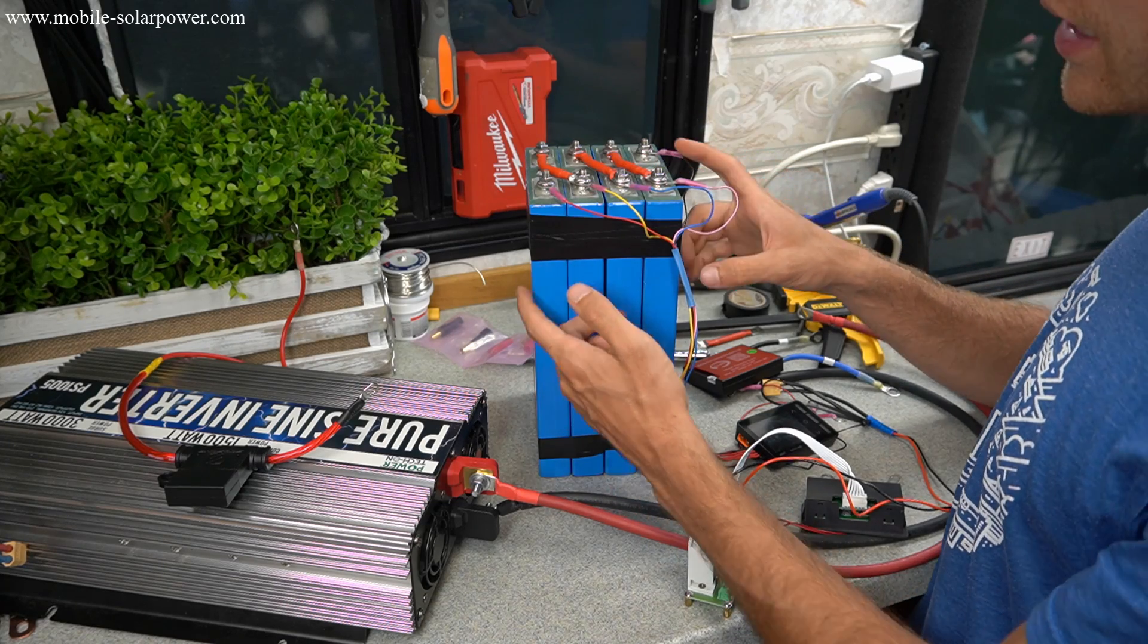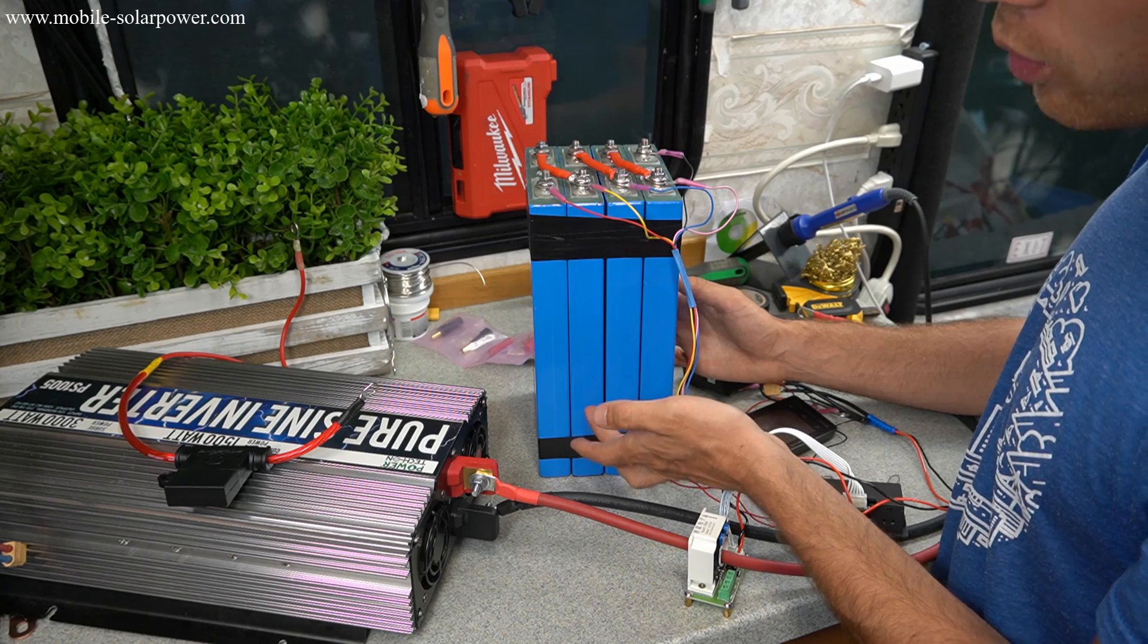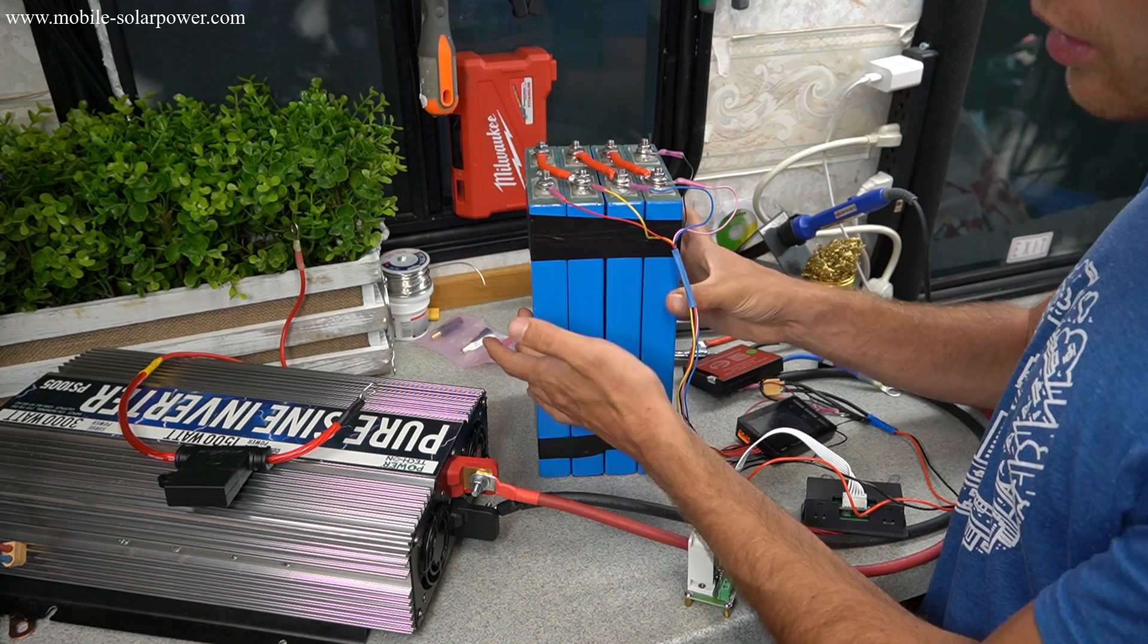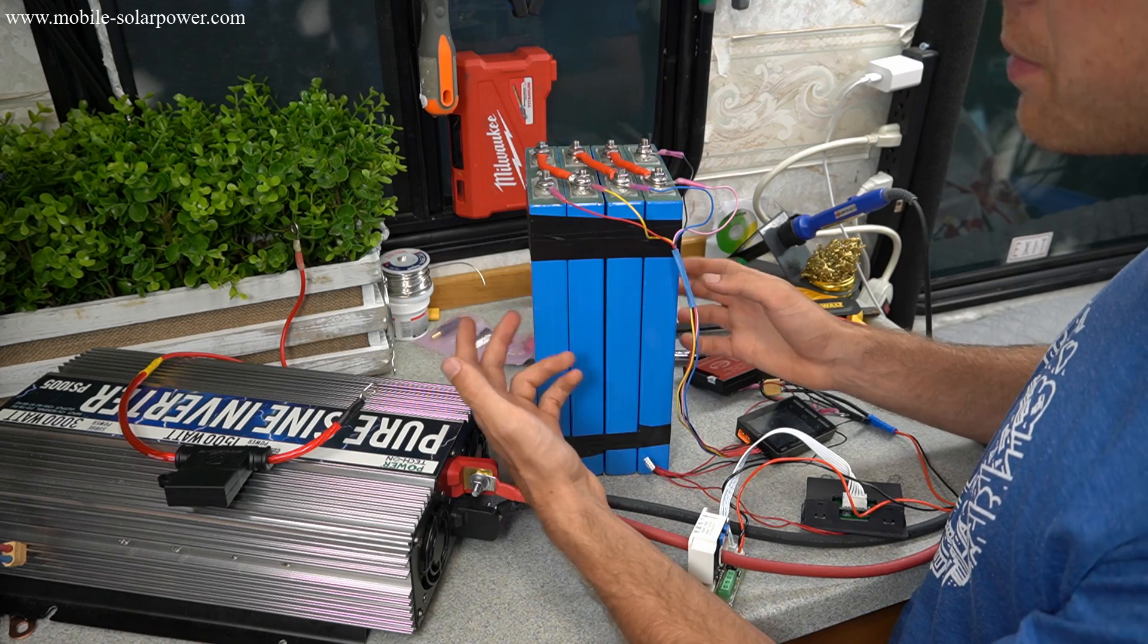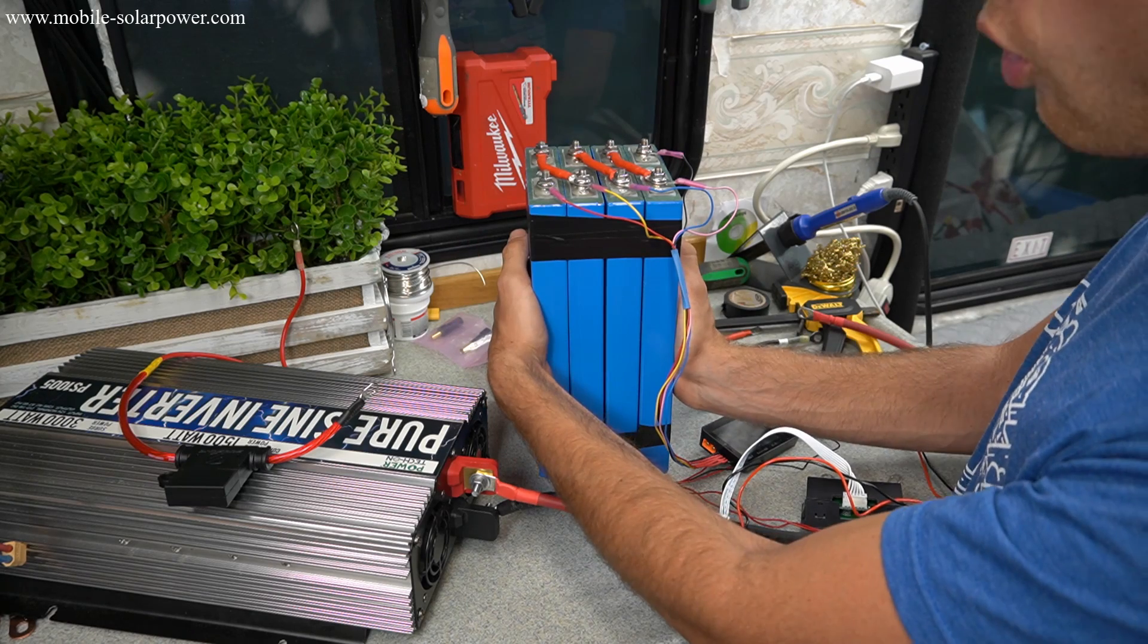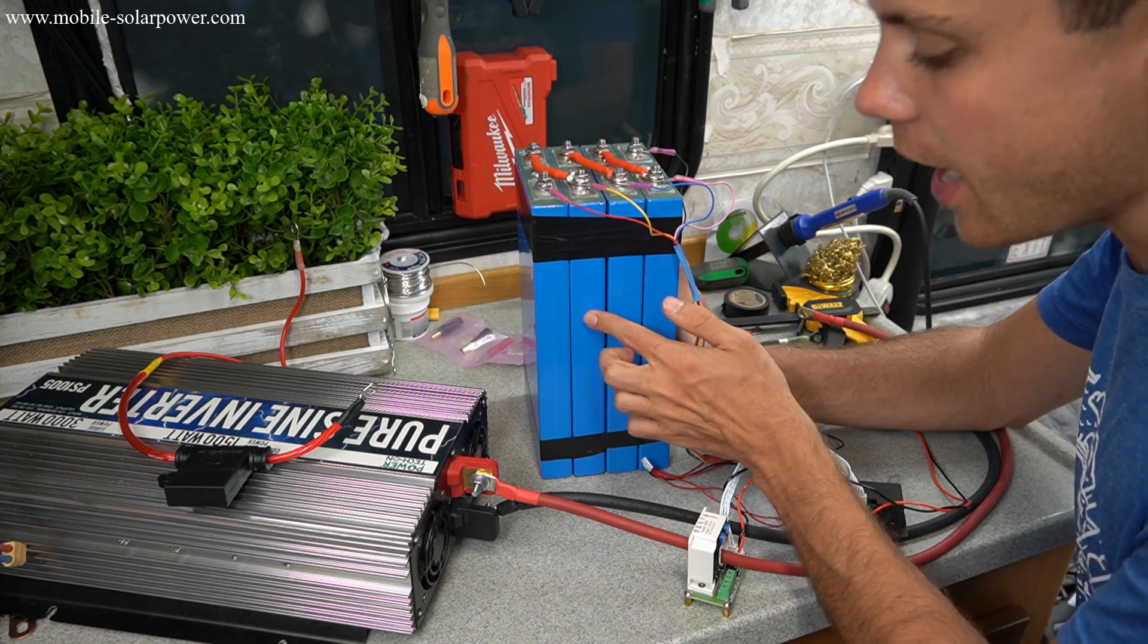And the reason that we do a capacity test is it will tell us how well these cells are matched and their overall health. So if one of the cells has lower capacity than the other ones, we will see it on the test, because the capacity of all of these cells is determined by the lowest capacity cell. So if all of them are good, then the pack as a whole will work really well in our capacity test. If one of them is bad, then our capacity test will have bad results.